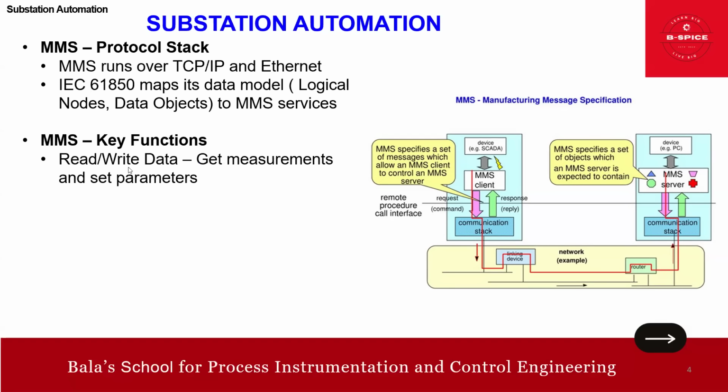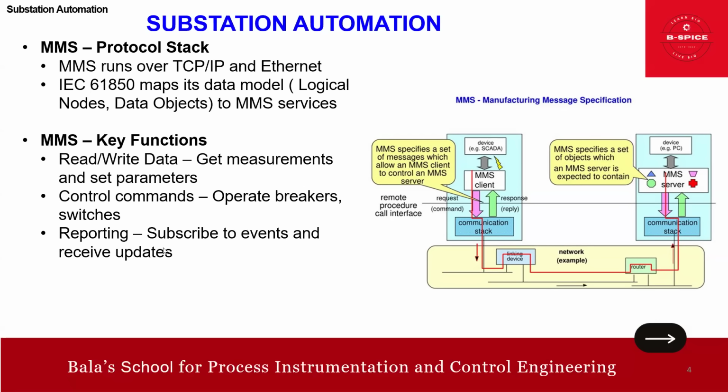It reads and writes data, gets measurements and sets parameters. This is very important. Then control commands, meaning it operates breakers and switches. Of course, reporting: it subscribes to events and receives updates. These are the key functions: read and write data, control commands, reporting and receiving updates.